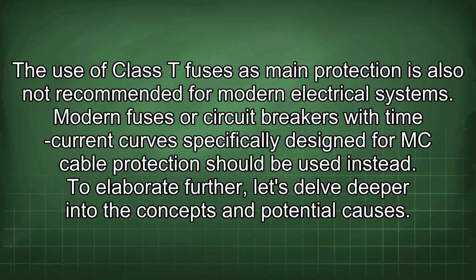The use of Class T fuses as main protection is also not recommended for modern electrical systems. Modern fuses or circuit breakers with time current curves specifically designed for MC cable protection should be used instead. To elaborate further, let's delve deeper into the concepts and potential causes.